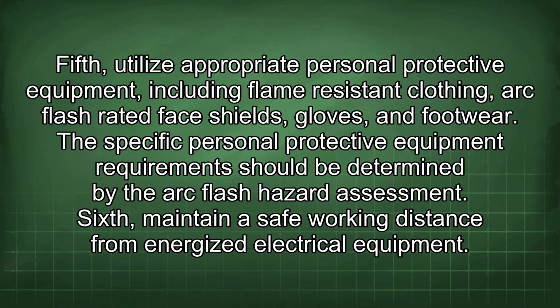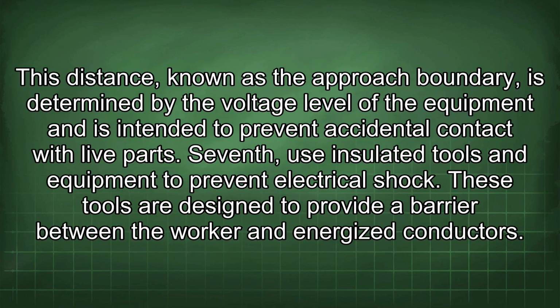Sixth, maintain a safe working distance from energized electrical equipment. This distance, known as the approach boundary, is determined by the voltage level of the equipment and is intended to prevent accidental contact with live parts. Seventh, use insulated tools and equipment to prevent electrical shock. These tools are designed to provide a barrier between the worker and energized conductors.